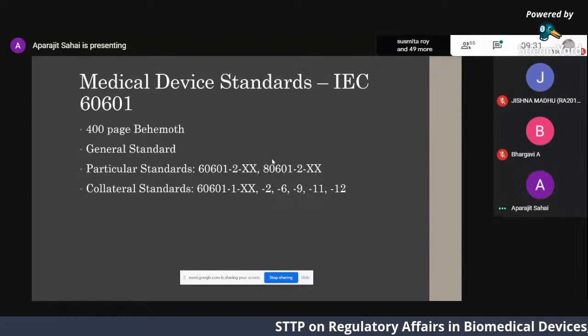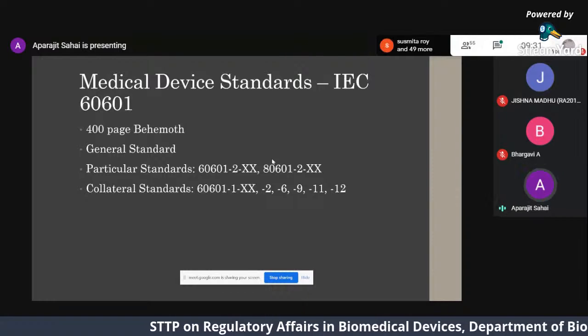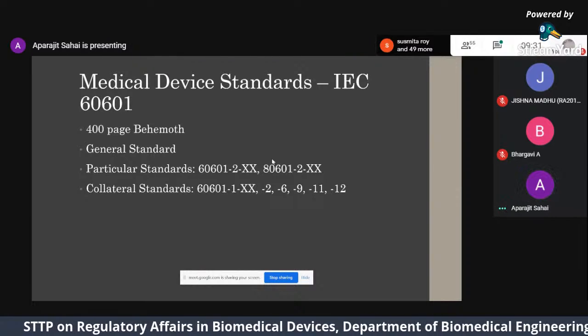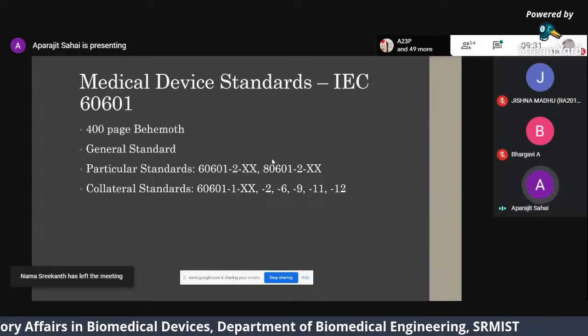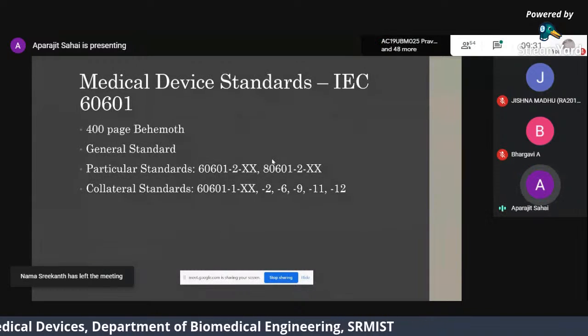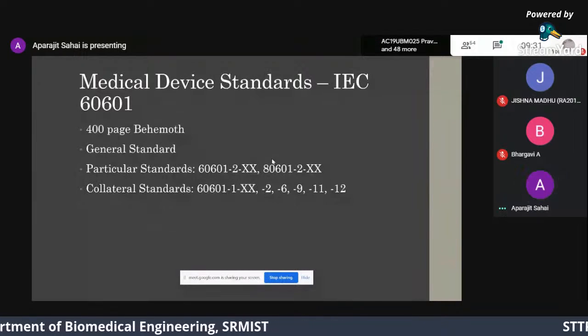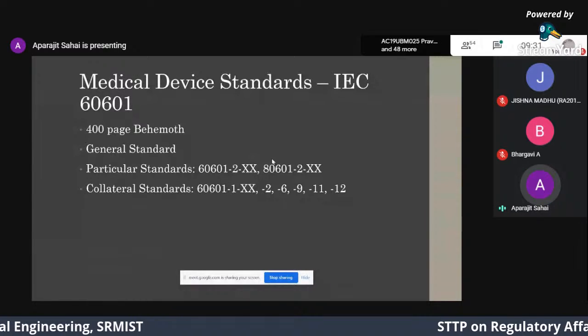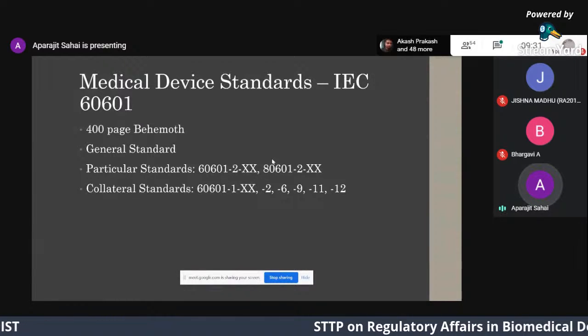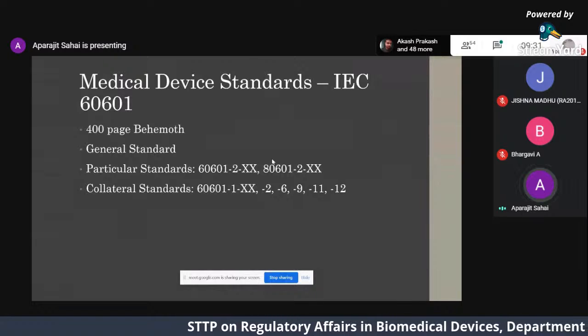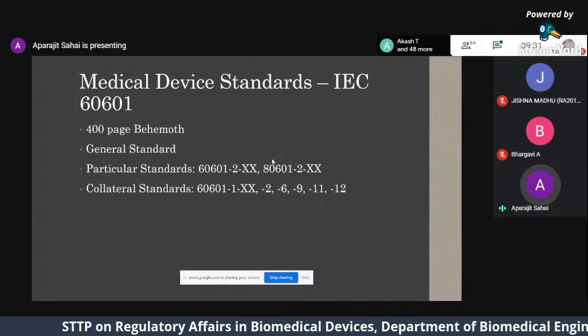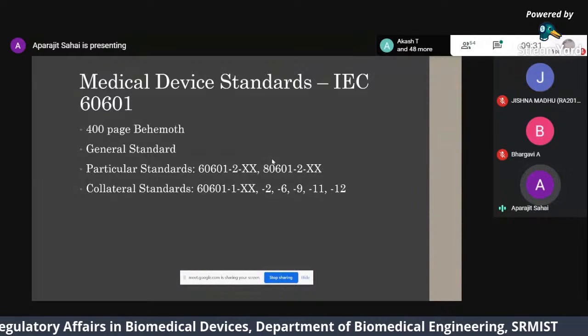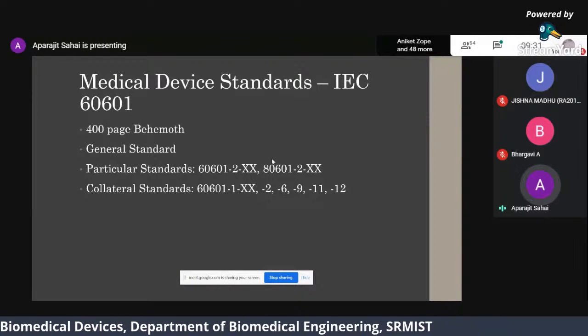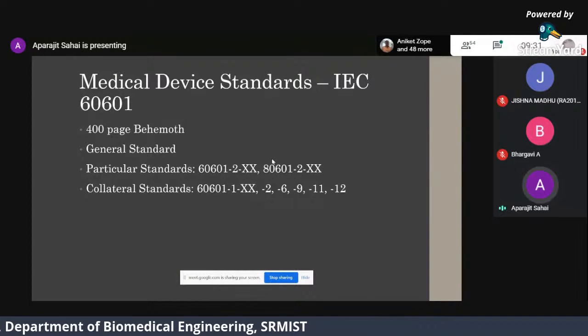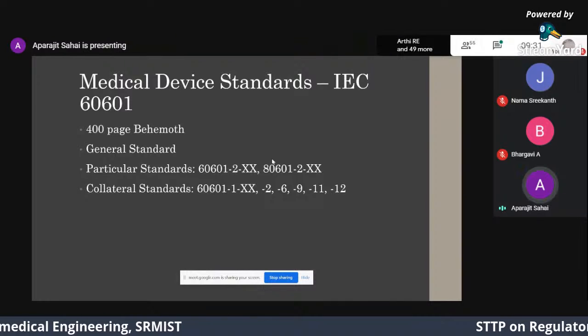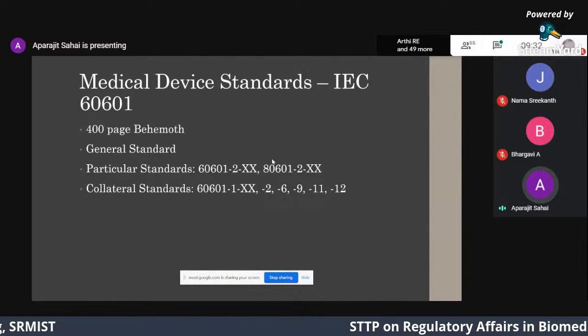So these are all general requirements. And then you have particular standards, which you will see. Usually IEC 60601-1 is general, and then you have particular standards which would be designated with 60601-1, 60601-2, whatever number. So let's say I think -27 would be your ECG standard. -51 is LEDs that are used in therapy, and then there's 22, I think, which is lasers, and then of course 37, which I work with a lot, is diagnostic ultrasound.